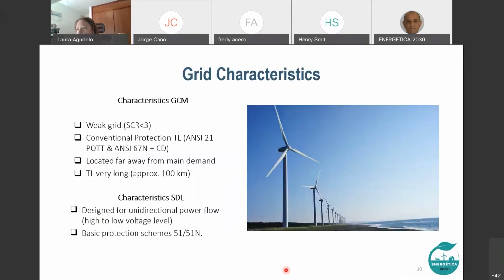Next, please. In this slide, I would like to mention some characteristics of the GCM grid and the distribution system. From the point of view of protection, inverters are characterized by low contribution of fault current, contribution of positive sequence current with almost zero negative sequence but close to 0, high sensitivity to voltage dip, modification of the current angles, and others. For this reason, the manufacturer of the inverter recommends connecting this equipment to strong grids, with a short circuit ratio of 3 or higher. And at this moment, the GCM area is characterized by a weak grid.